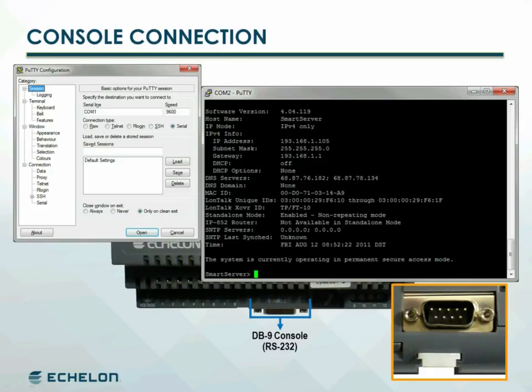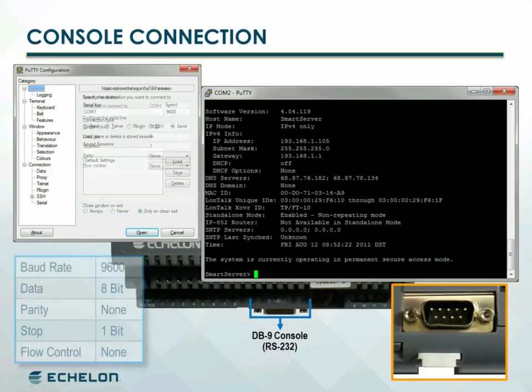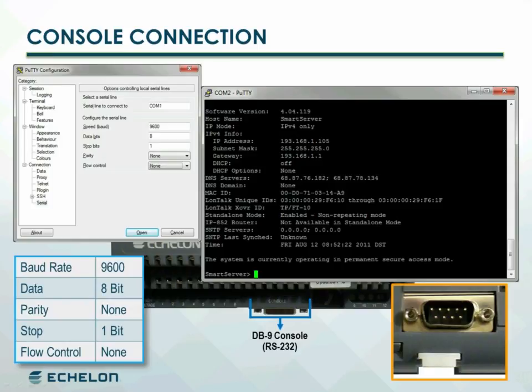PUTTY can also be used to communicate with the SmartServer over Telnet. The console default communication properties are 9600 bits per second, 8-bit data, no parity, one stop bit, and no flow control.